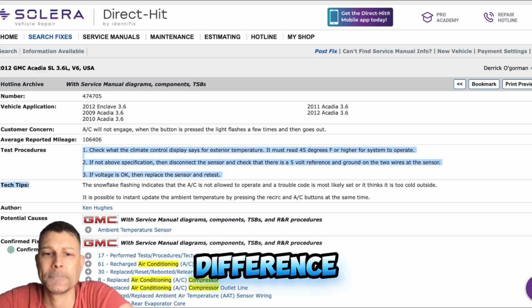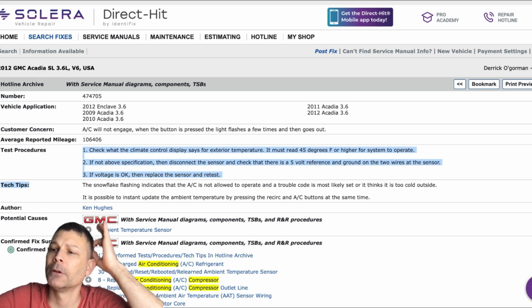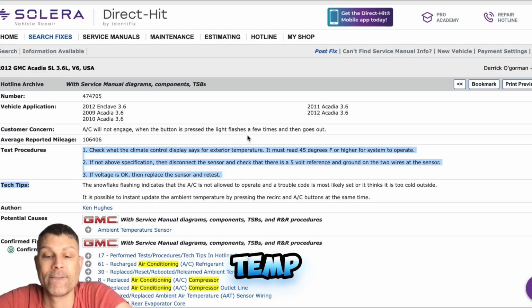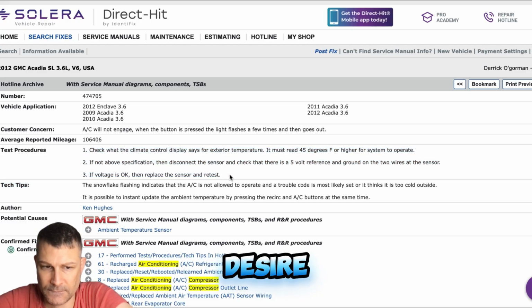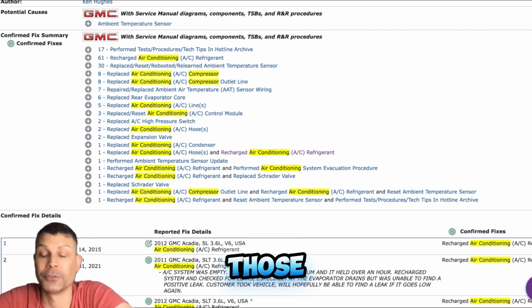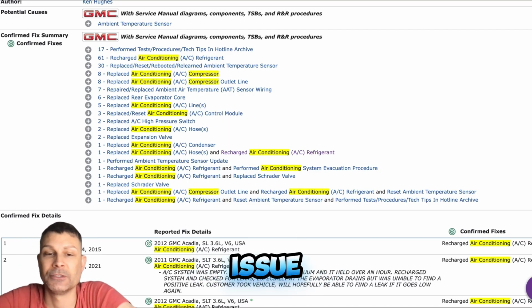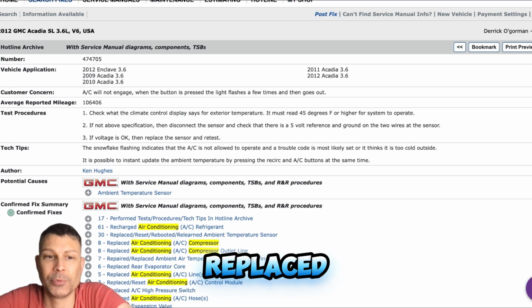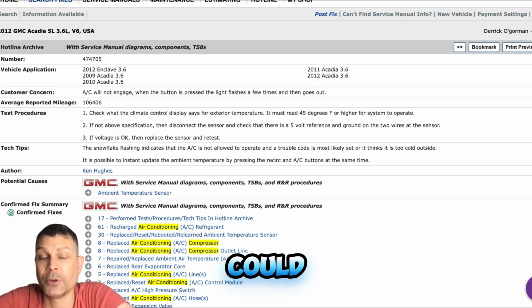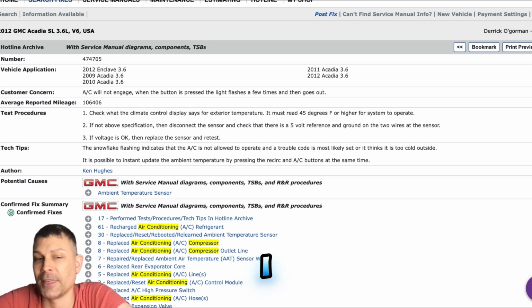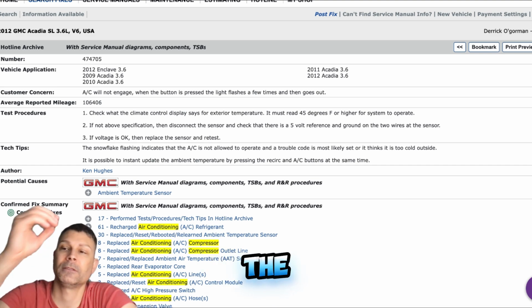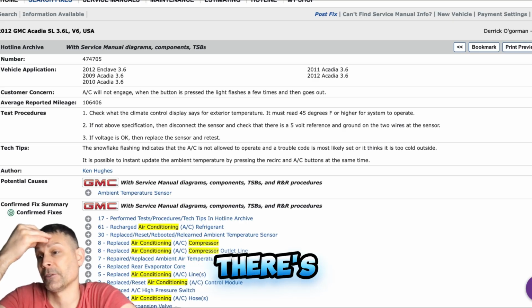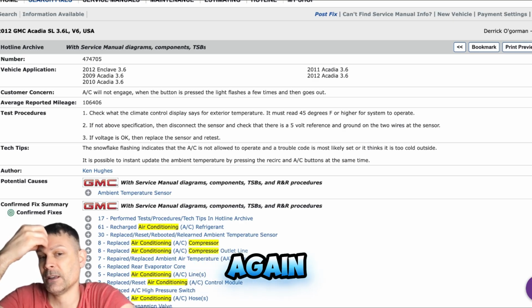Right, it's a big difference right there. Yeah, that could be an issue. Is that Fahrenheit? Evap temp sensor filter 93, evap temp sensor raw 93. Everything's around 93 except the desired temp. Yeah, one of those 3 inputs to the computer is causing this issue. So if the pressure sensor has been replaced, we could look at the other ones. You could back probe that pressure sensor that you replaced to see what the signal is. I think it might be a little difficult to get to the evaporator temperature sensor, but then there's the ambient air temperature sensor. What does that say again?